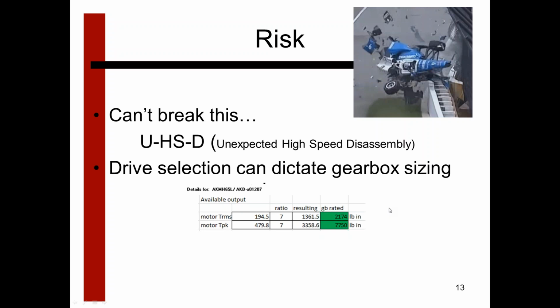So I had an application with a customer where we had a choice. The motor was picked. The drive required for his application was based on continuous current. So we were able to pick a relatively small drive with respect to peak current. But the motor nameplate had a lot higher torque output. So I had a conversation with him and asked him, by the way, you could buy the next larger drive. With that drive, it's the same footprint in your panel. That's pretty typical that various drive frame sizes will have different current outputs. So I pointed out to him, without any more square inches inside your panel, for a few hundred dollars more, you could have a lot more torque output if you think you might need it down the road.